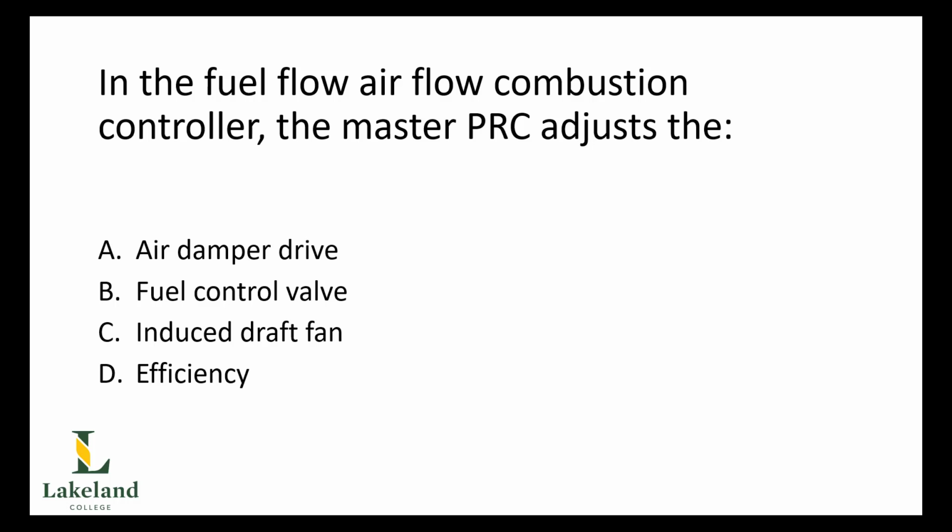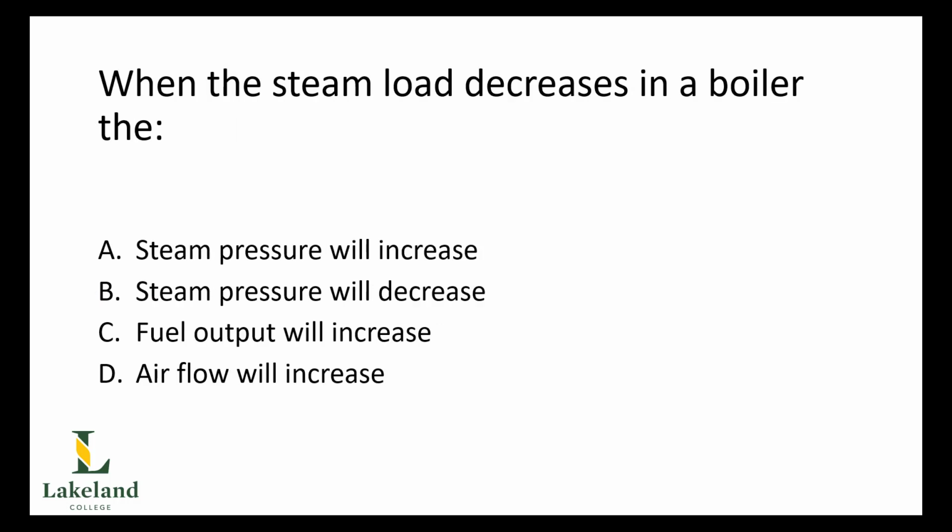Next one. In the fuel flow airflow combustion controller, the master pressure recording controller adjusts what? The air damper drive, the fuel control valve, the induced draft fan, or the efficiency? Well, once again, take a look at the diagram and take a look at what's located directly below the master pressure recording controller. And that is the fuel control valve, because it's the gas flow and airflow transmitters via the FRC that are going to position the air damper drive. So again, it's a question relating directly to the diagram.